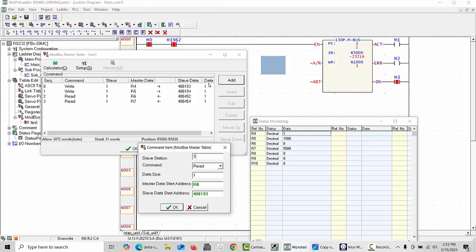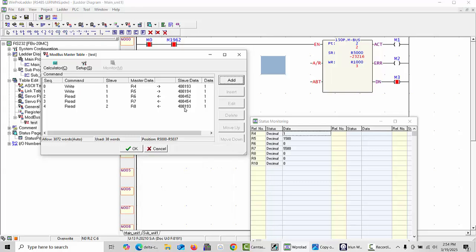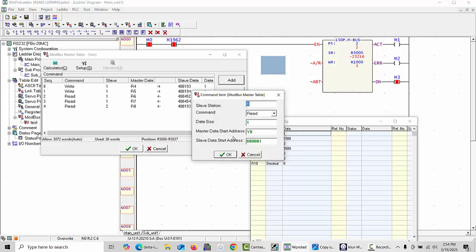This is the first VFD, these are the first VFD parameters, and now we will write for the second VFD. So the address we give in the VFD is 2, and here we will also give 2. If you have another brand, also no problem, you just have to set these parameters according to the manufacturer's advice, whichever numbers he gives, you have to write those numbers here. So this is ready. First our command address, click OK and your data will be ready. And next you have to choose one more data register. You can see here the slave address is now changed.